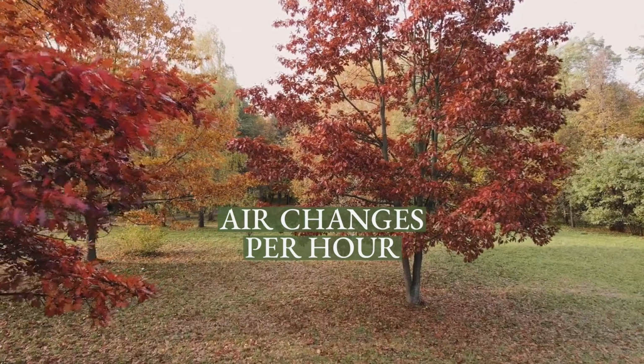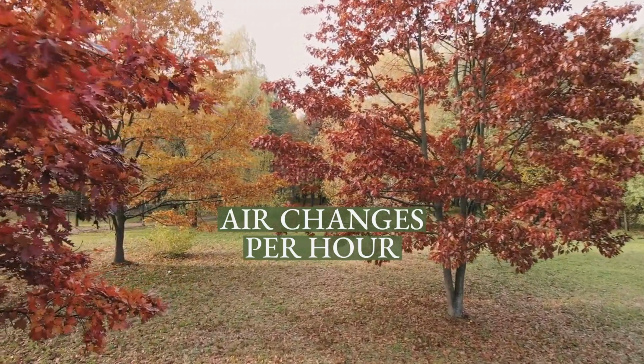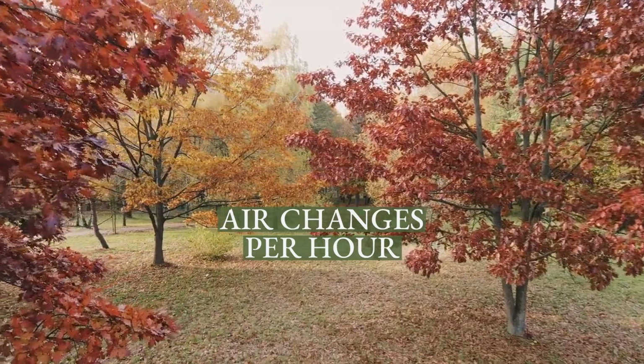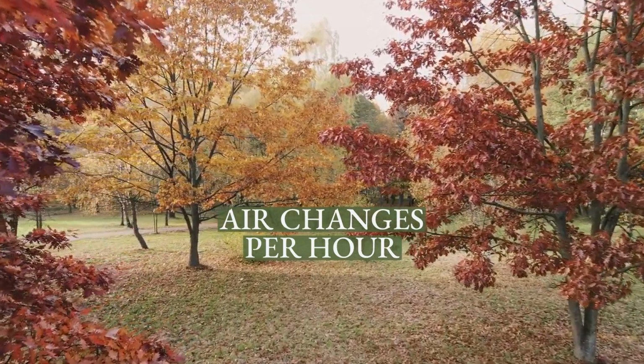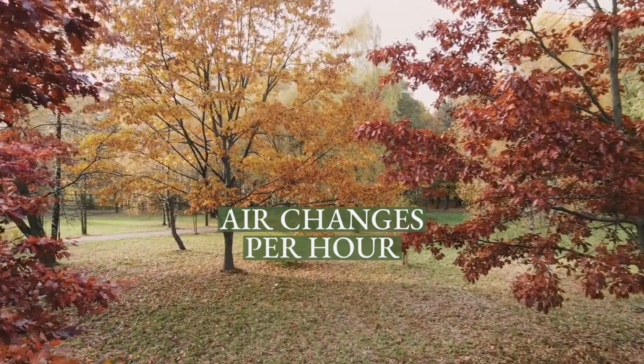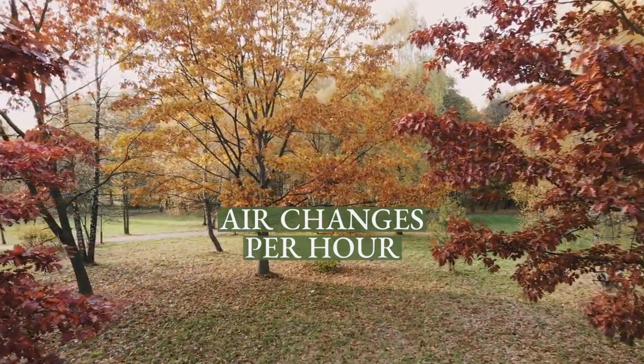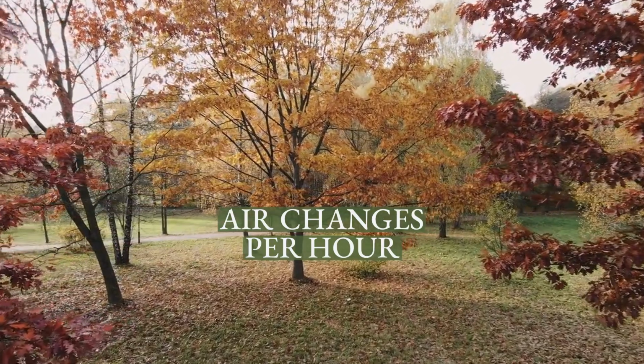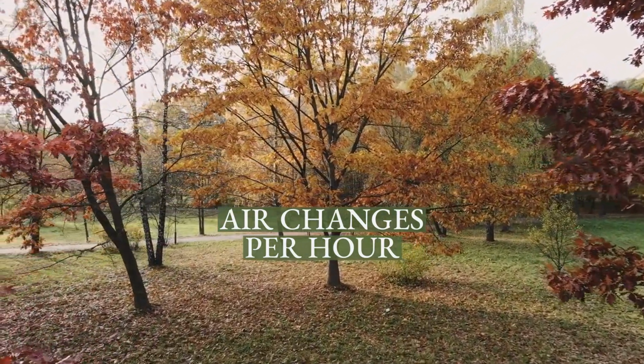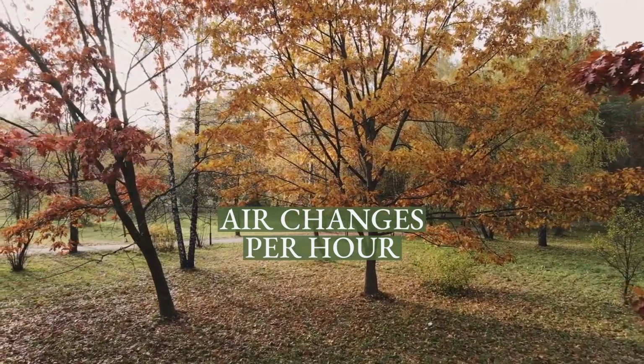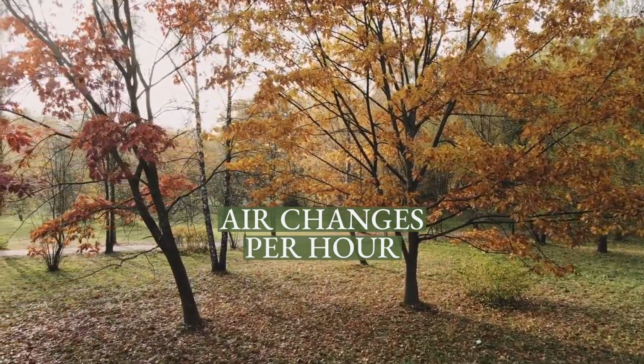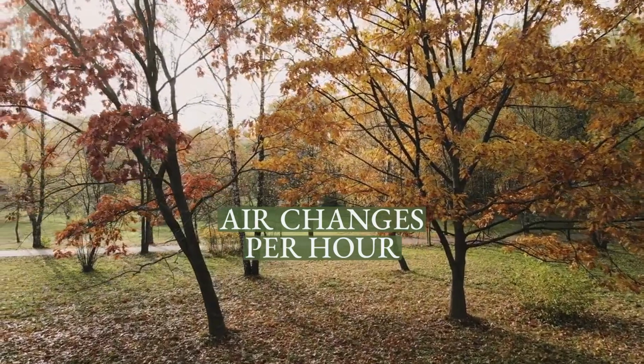Let's now zoom in on air changes per hour and uncover the hidden gems that lie within. In imperial units, ACPH = Q × 60 / Vol, where ACPH equals number of air changes per hour, higher values corresponding to more ventilation. Q equals volumetric flow rate of air in cubic feet per minute. Vol equals space volume, L × W × H, in cubic feet.